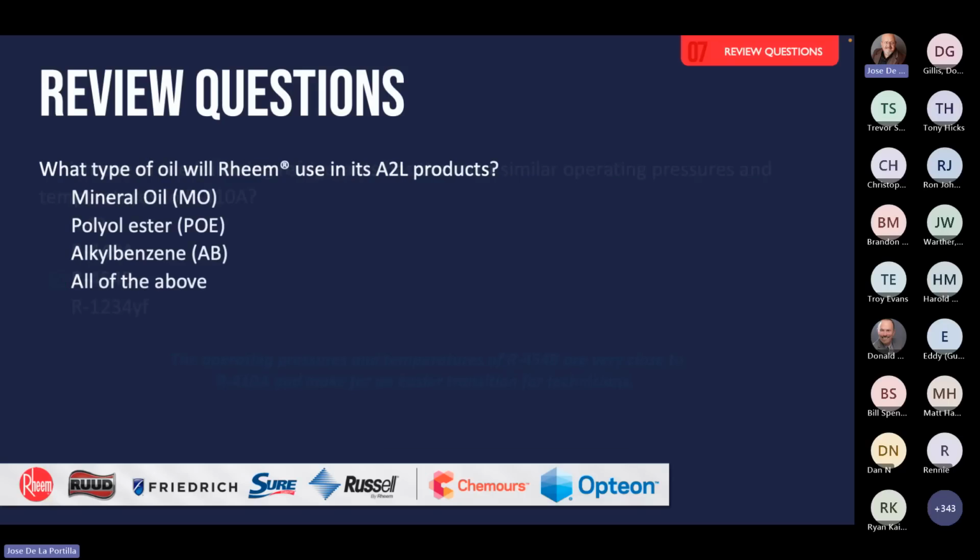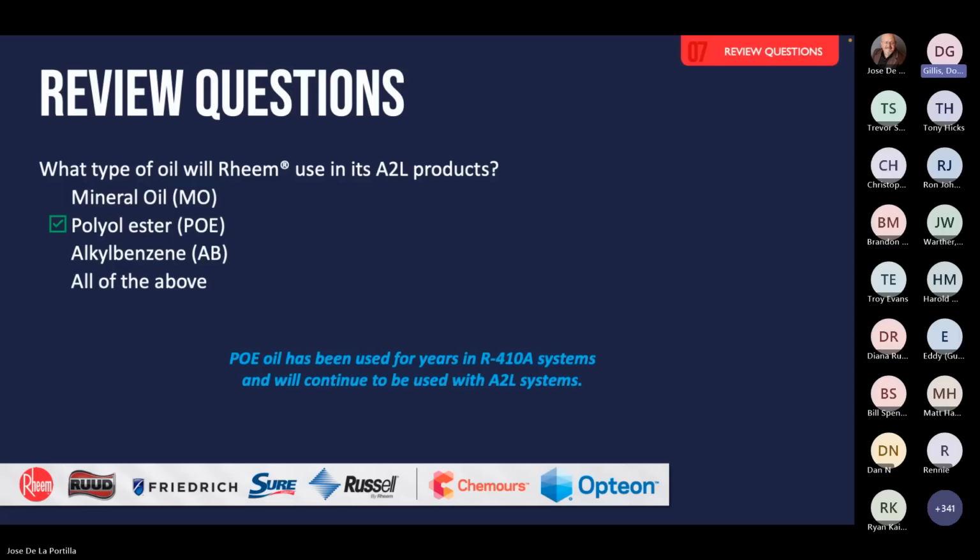So we'll jump over to this next one, Don. What type of oil will Rheem use in its A2L products? Mineral oil, polyester oil, alkylbenzene, or all of the above? And the answer is polyester oil, POE. As Jose said earlier, the POE will be the same as it was for 410A, POE 32. If you're moving to the R32, as Jose said, it runs a little hotter and causes a little more friction, so they're going to go with a POE 46. I would refer you back to Emerson's AE Bulletin 93-11.